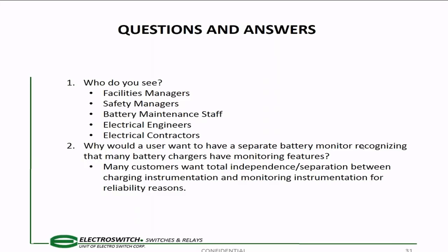Second question, why would you want to use a separate battery monitor, recognizing that many battery chargers have monitoring features? So, the first reason I always use when I talk to people is that when I go to Battcon, and I've been several times, and we go every year, the battery experts say, if you want to monitor your battery, monitor your battery. An AC charger is an AC charger, monitor your battery, okay? Your AC chargers may have some monitoring features. A lot of times, you don't have independent outputs identifying what the alarm is, so you have to send somebody out into the field to find out, hey, do I have a ground? Do I have a high-low voltage? Do I have a loss of AC?